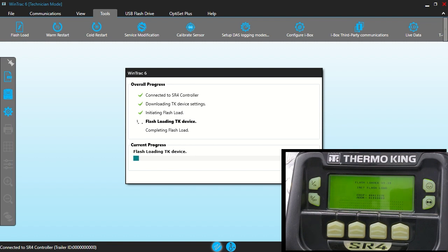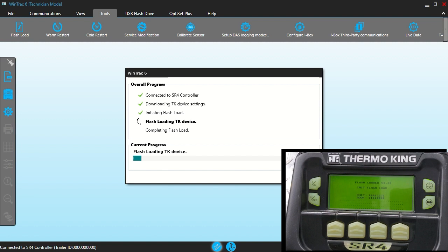Another important thing to remember is that if you're upgrading the software that's on the unit, you want to flash load the controller and then the HMI like I did here. But if you're going to back flash or put older software back on the unit than what's on it currently, then you want to do the HMI first and then the controller.